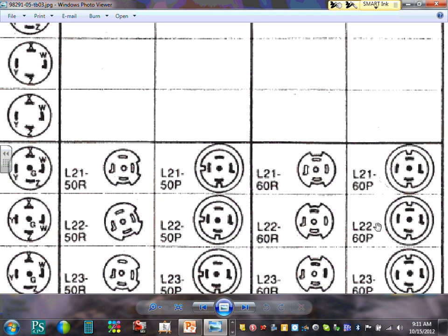Now, some of you looking here said, are you kidding me, Chad? Where would we use something like this? You'll be surprised. That's how they're used in portable generators when they go to plug a portable generator into a lift station because you lost power in that section of Bloomington. And if you don't move that sludge, the street will be flooded with sewage, right? Is that a problem? So you take a portable generator right next to this lift station, plug it in, and lock it.